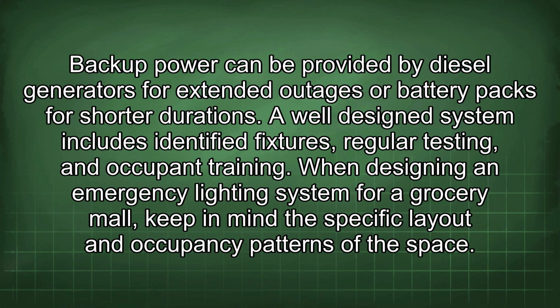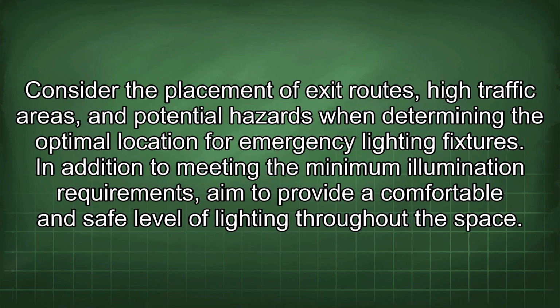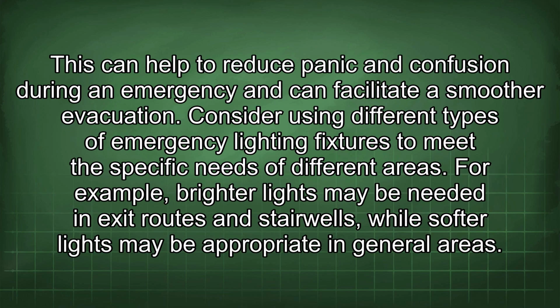When designing an emergency lighting system for a grocery mall, keep in mind the specific layout and occupancy patterns of the space. Consider the placement of exit routes, high traffic areas, and potential hazards when determining the optimal location for emergency lighting fixtures. In addition to meeting the minimum illumination requirements, aim to provide a comfortable and safe level of lighting throughout the space. This can help to reduce panic and confusion during an emergency and can facilitate a smoother evacuation.